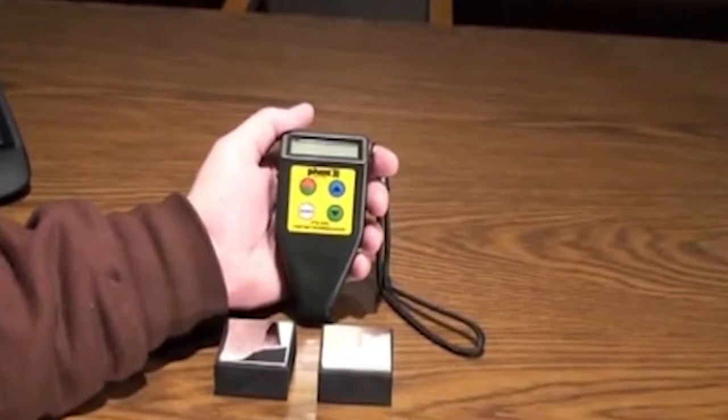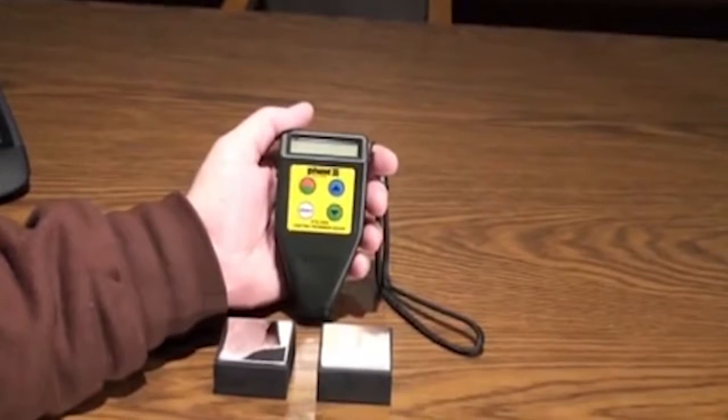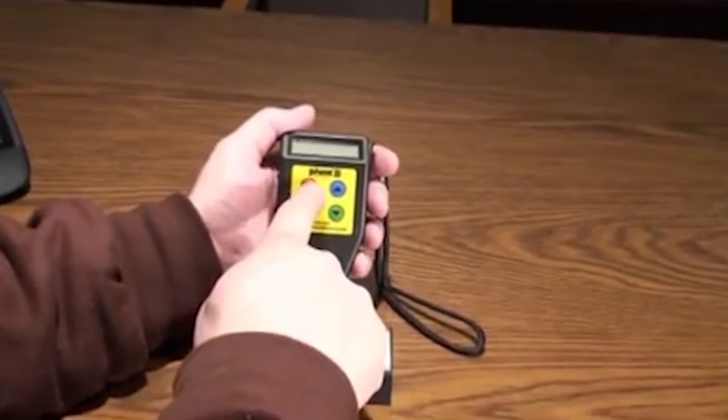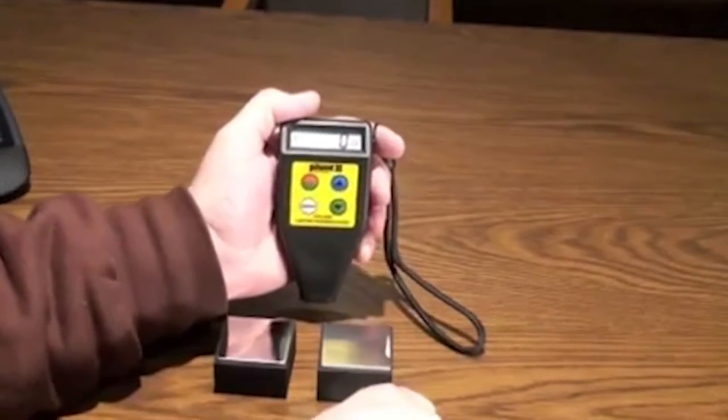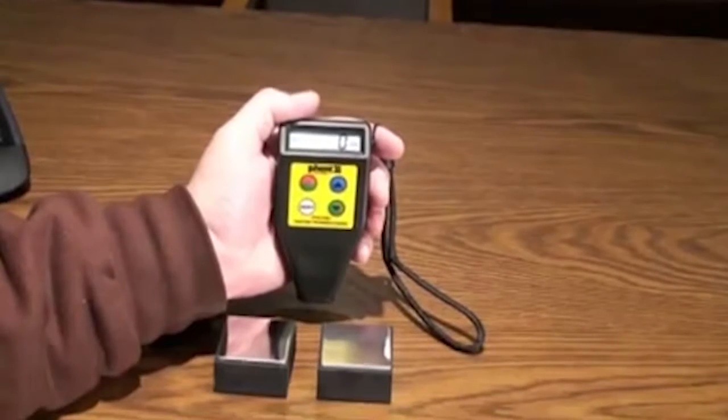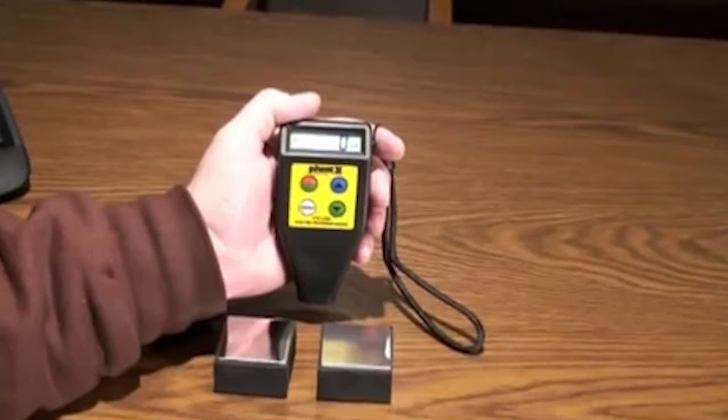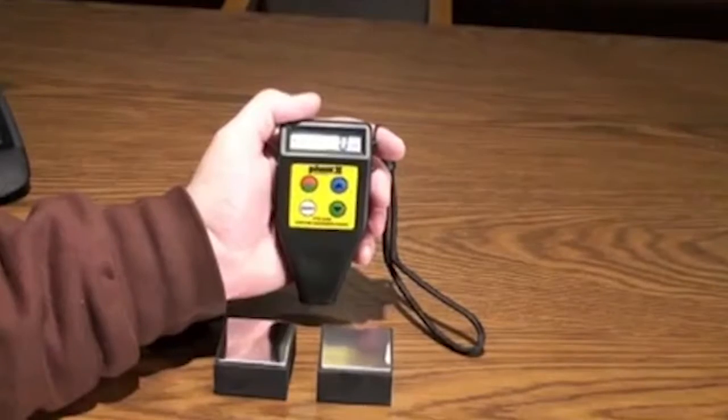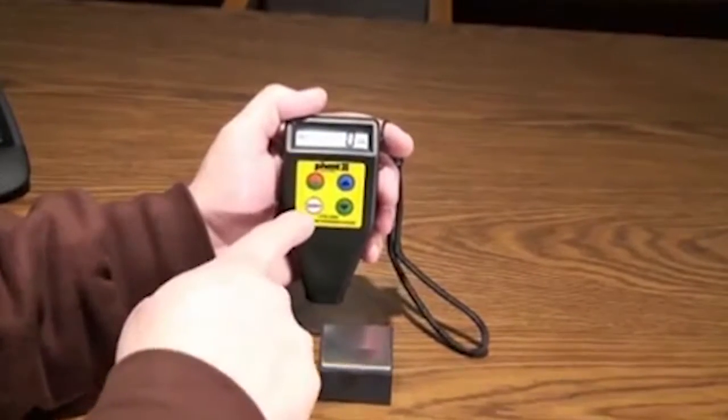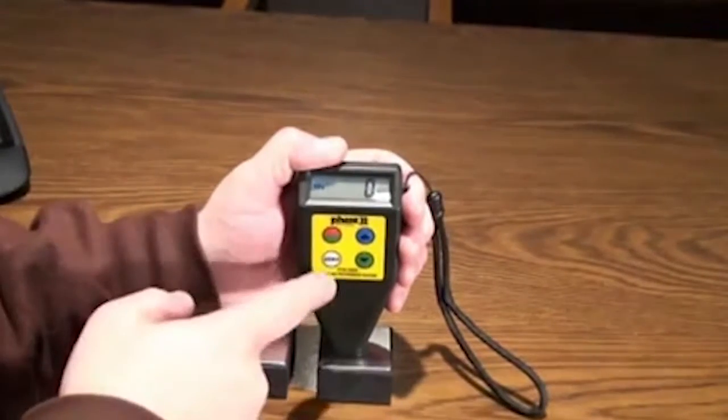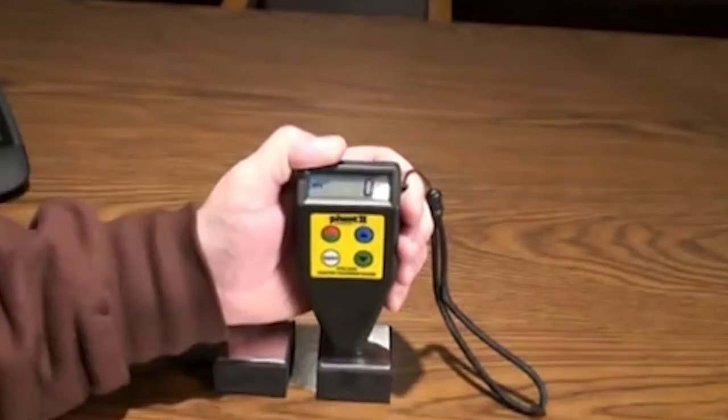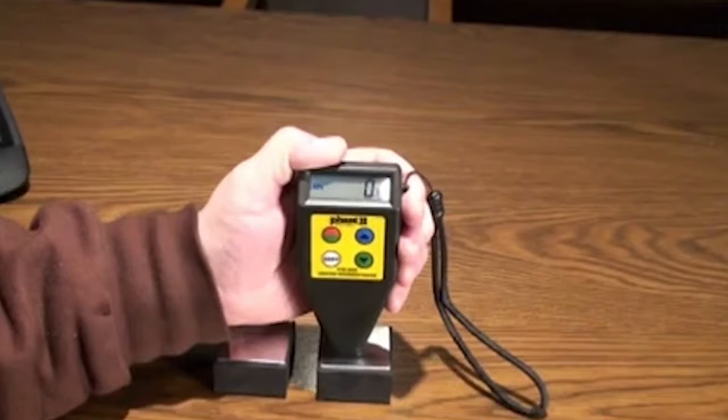Taking a test is extremely simple. Power up the unit pressing the red-green button. The unit is defaulting to UM since the calibration standards supplied are in UM microns. The zero key is designed to zero out the gauge on a substrate without coating. Place the gauge on a non-coated substrate and press the zero key while the probe is in contact. Zero will show on display.